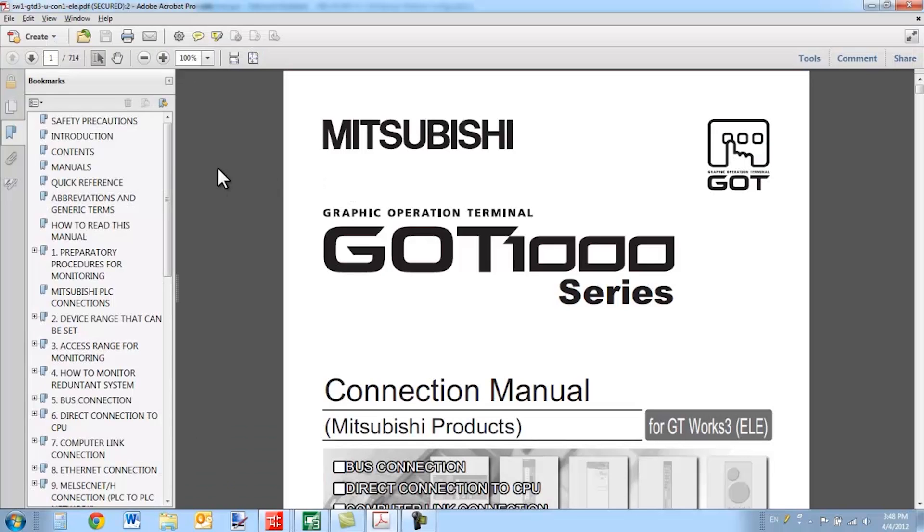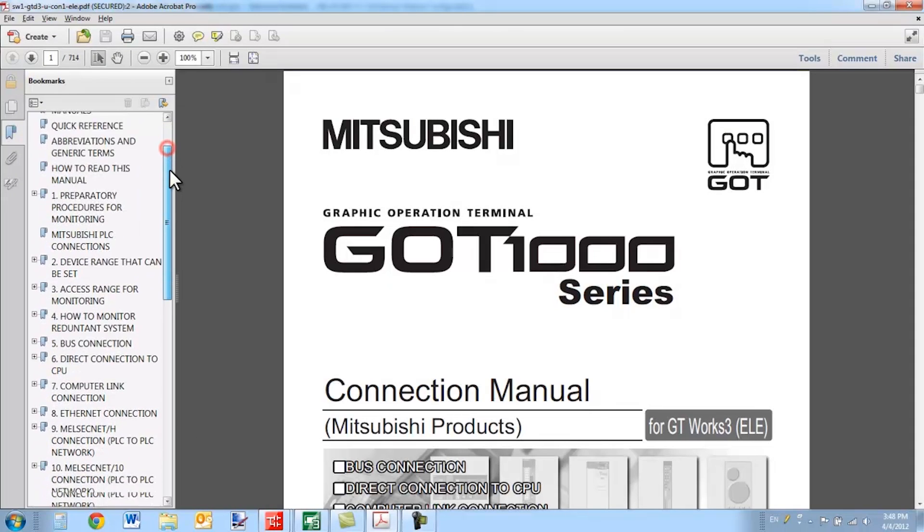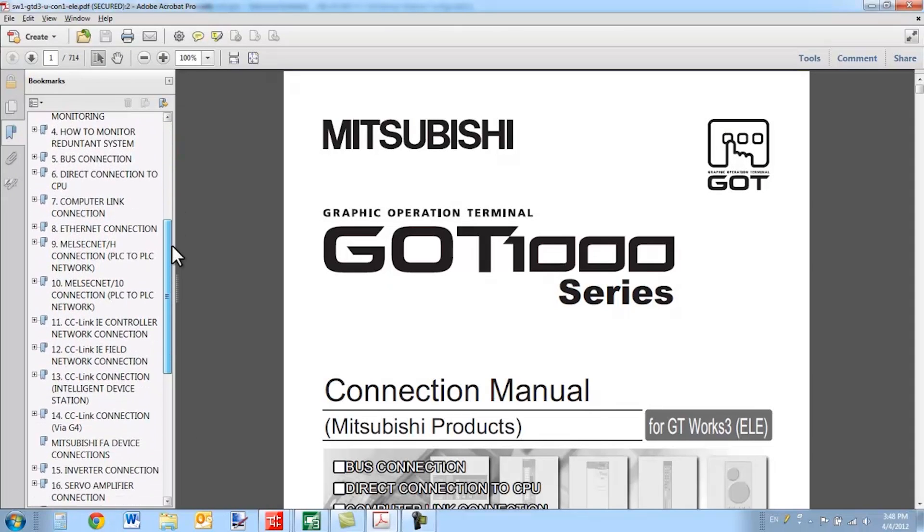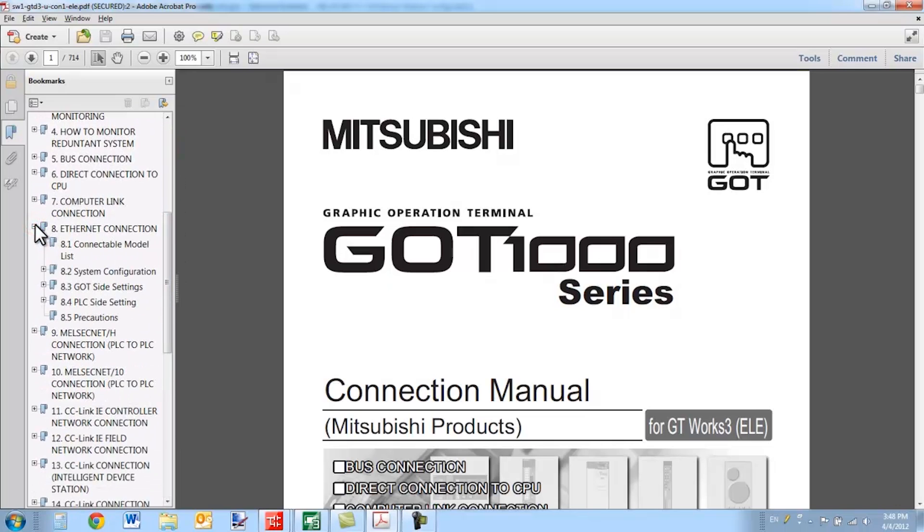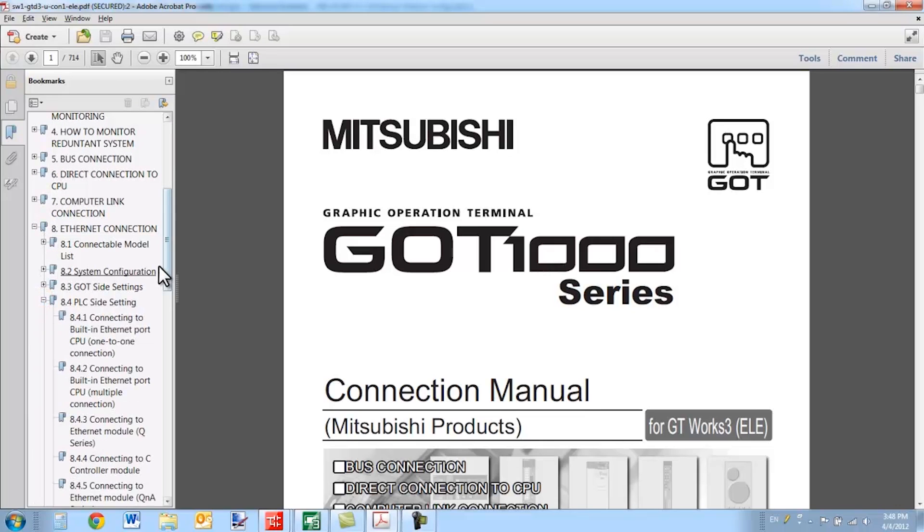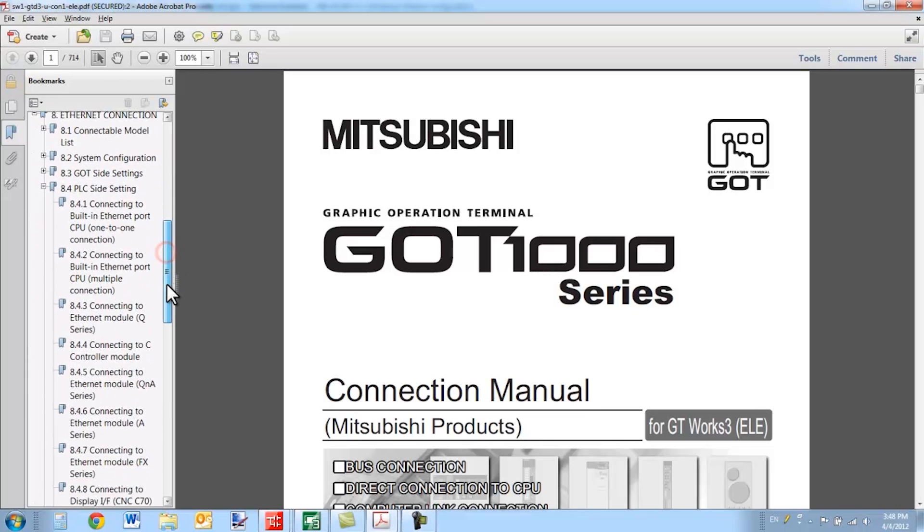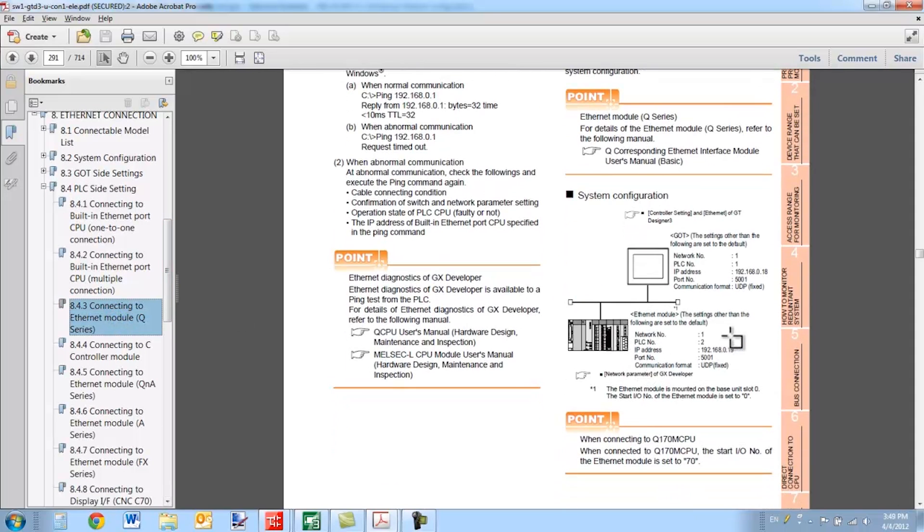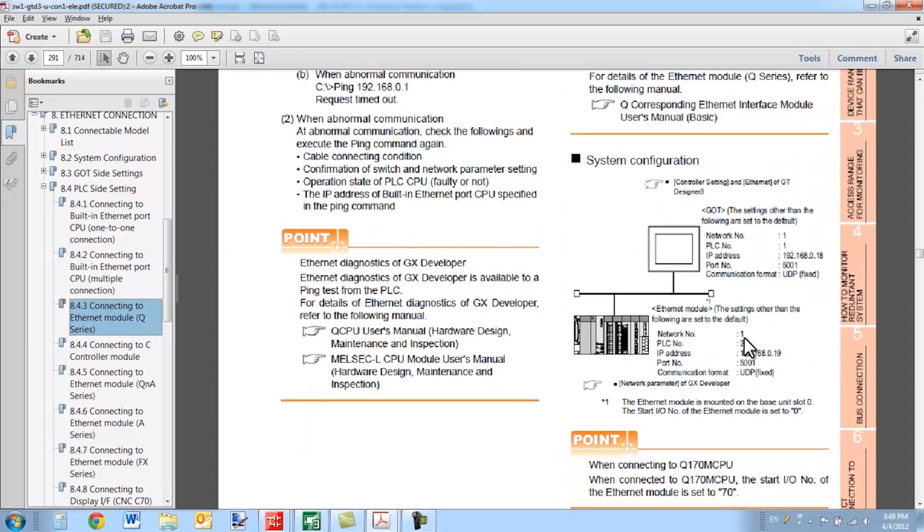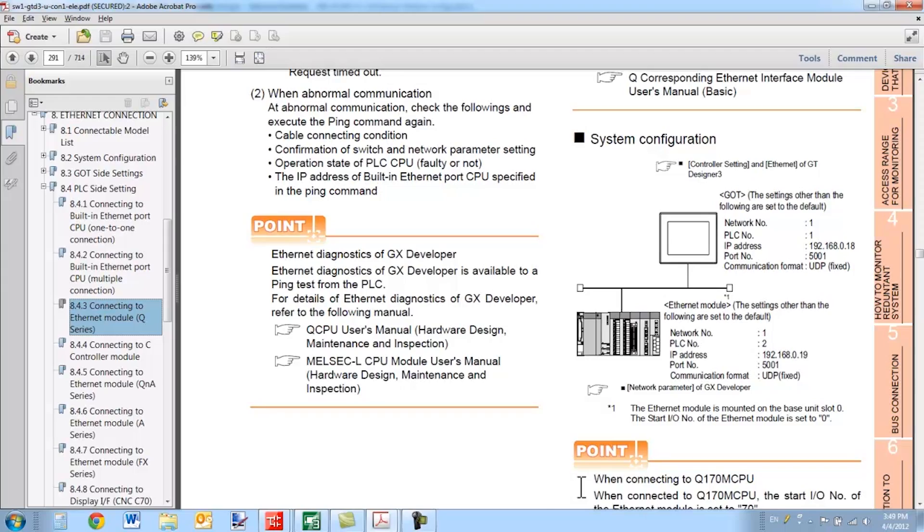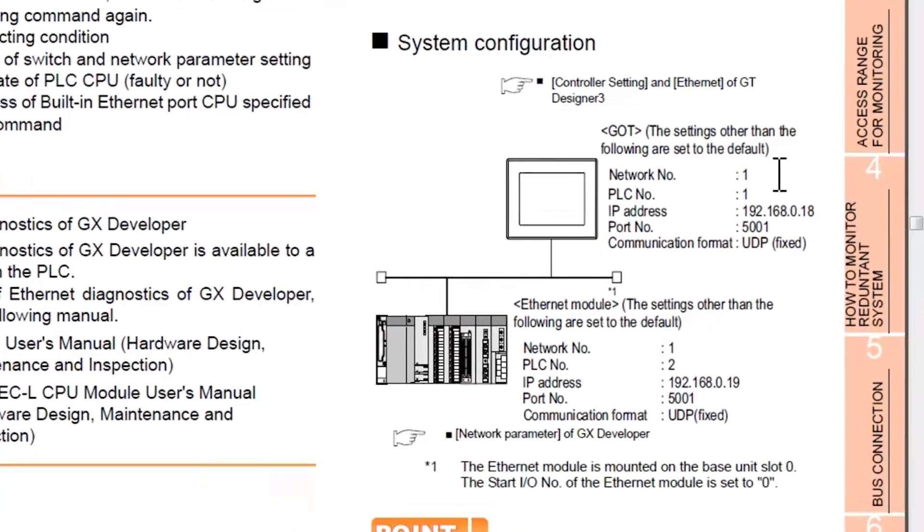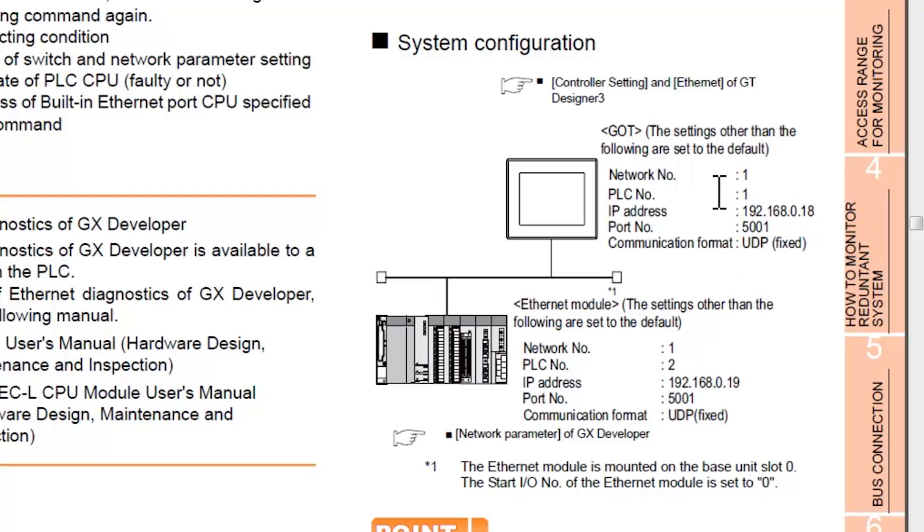Inside of this manual, if you scroll down here on the bookmark menu, you can select Ethernet connection, and then you can select your PLC side settings. In my case, I'm using an Ethernet module Q series. This diagram here gives you a nice overview of the setup you're using. So you have your network number matching the network number on the PLC. And for PLC number, the PLC number for the GOT is different from the PLC number for the Ethernet module. Very important.